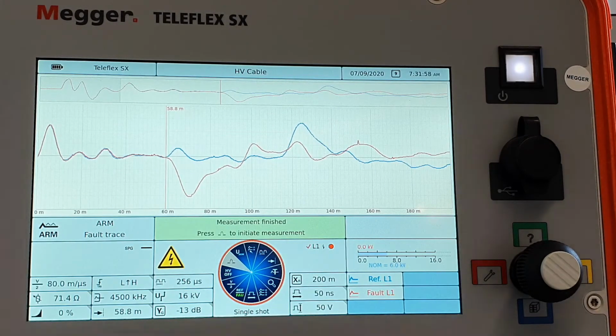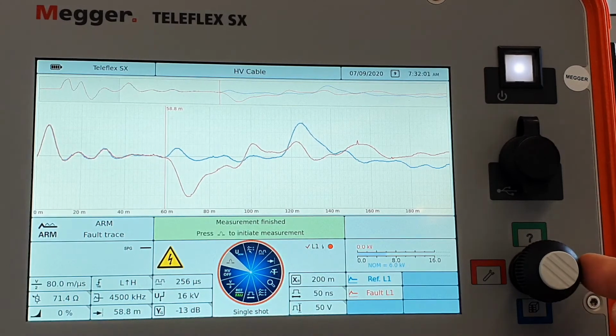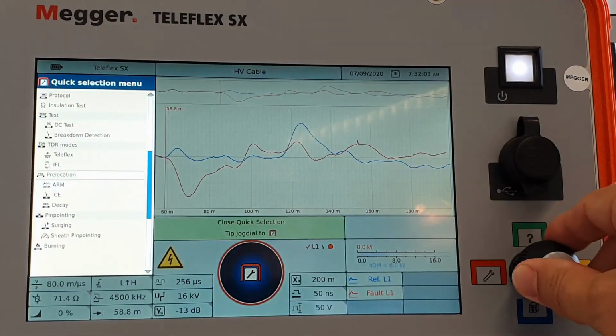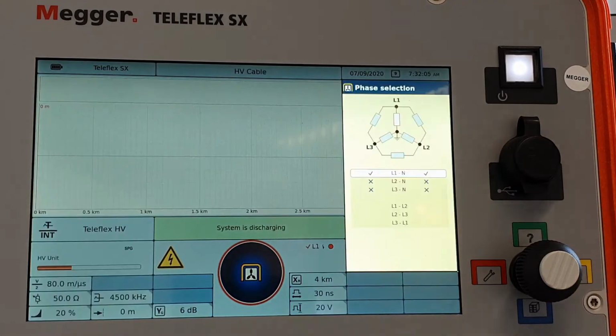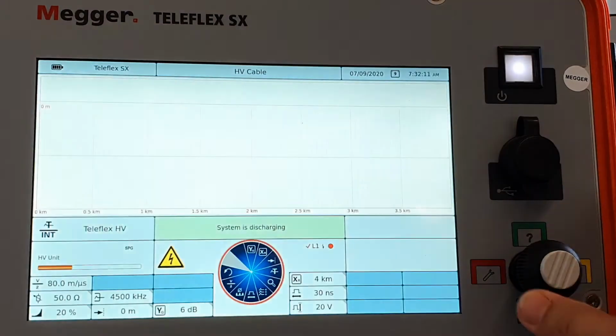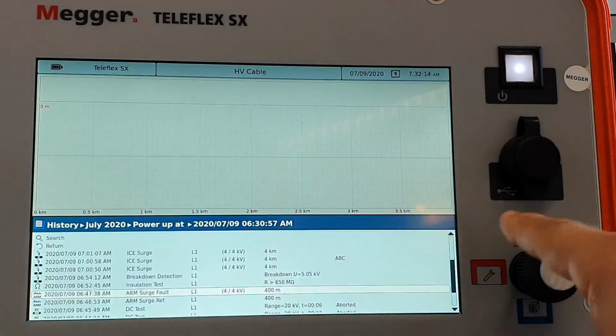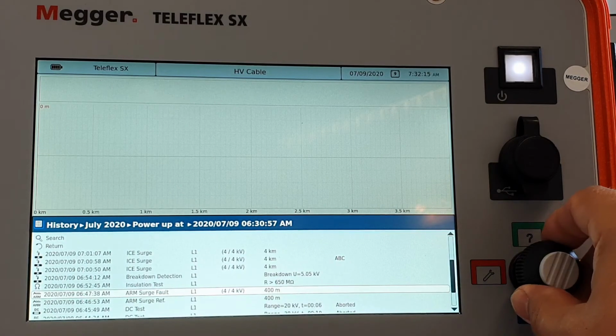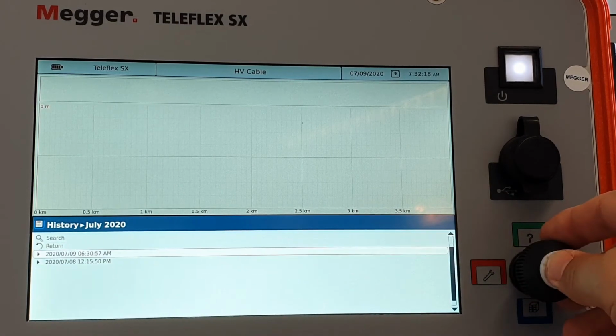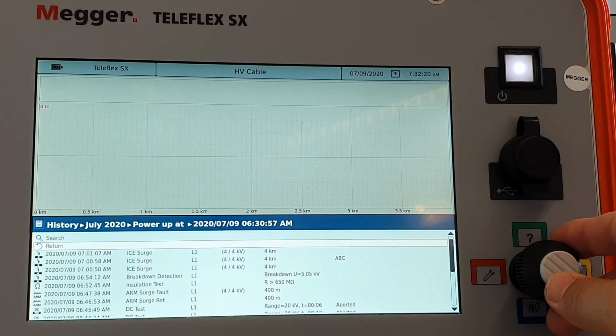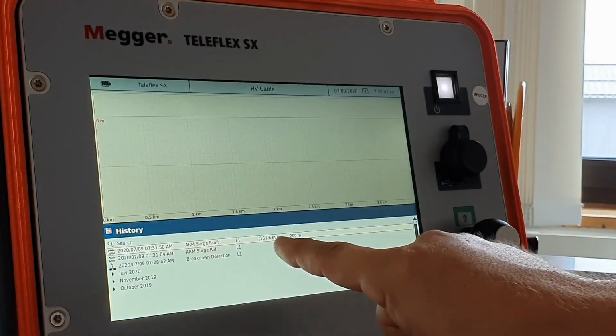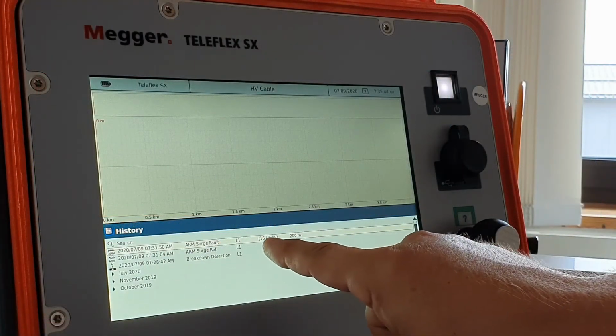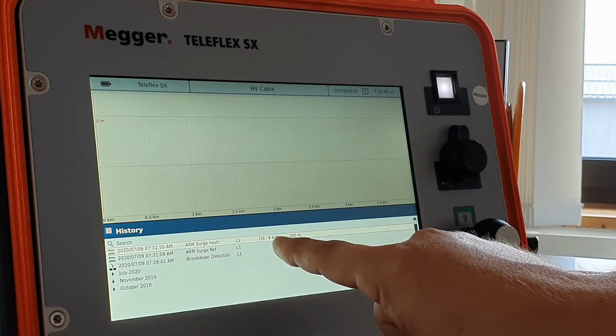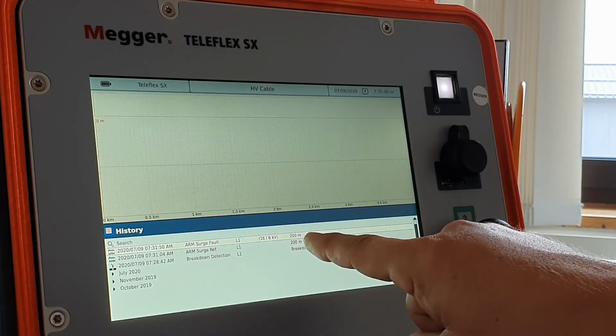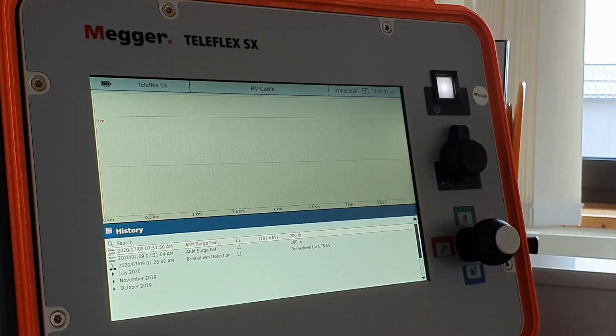This was arc reflection method. And the moment I leave this mode and go somewhere else, automatically the high voltage is switched off and I would find my measurement in the history. And I will see my measurement from just a moment ago. In the 16 kV range, I was using 6 kV in the measuring range of 200 meters.